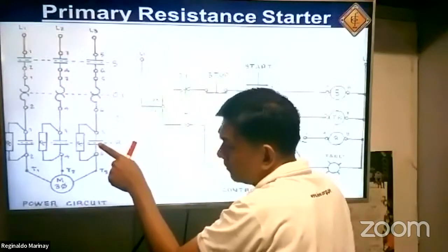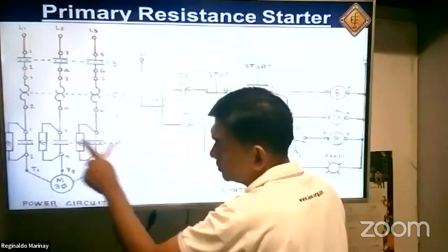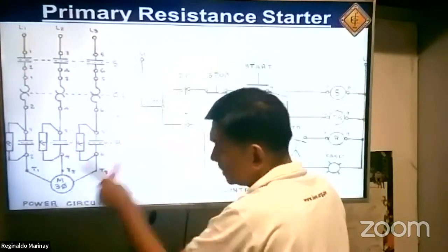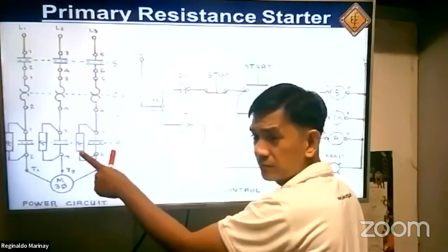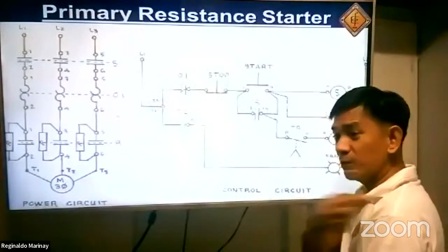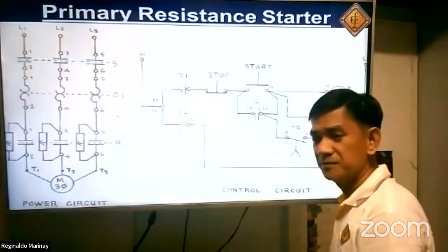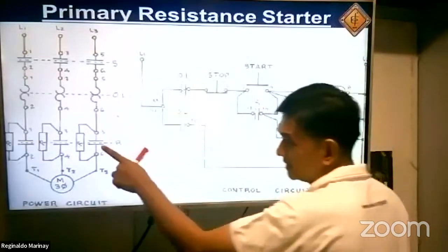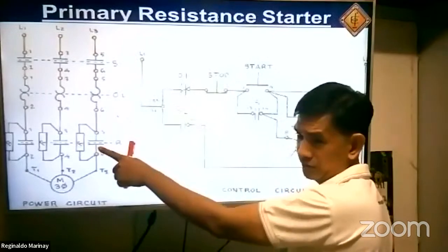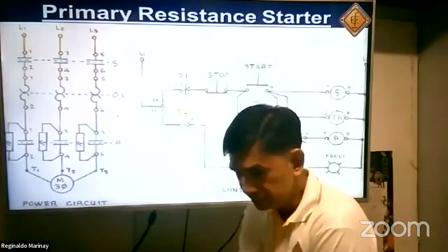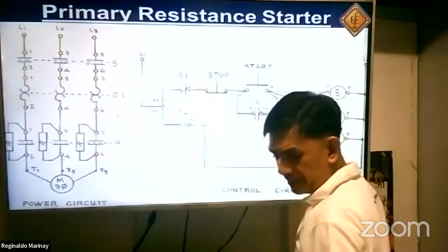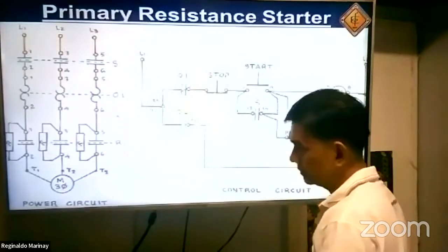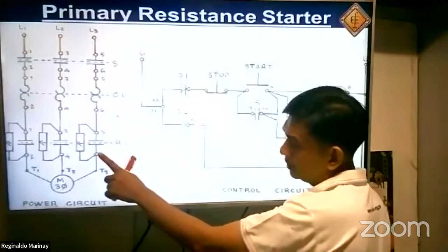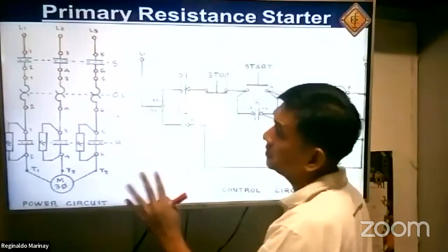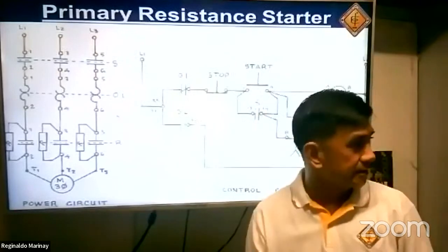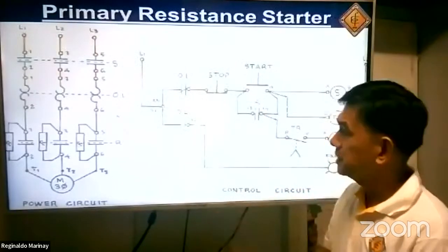Question: if your main contact R becomes short-circuited here, this becomes closed, is there any current flowing to the resistance unit? No more. Because of our principle before, I discussed with you, the bypass conductor. This acts as a bypass conductor. See? There is a bypass conductor. Okay? Take a look here. That is the basic idea of the primary resistance starter. That is the basic idea.